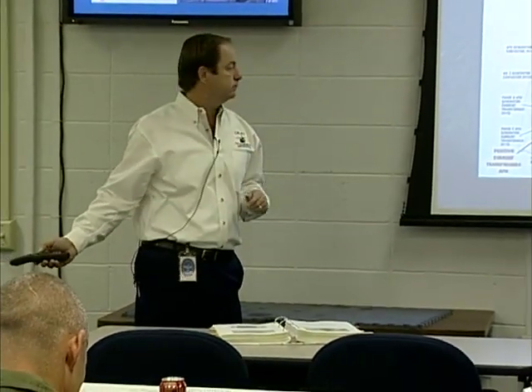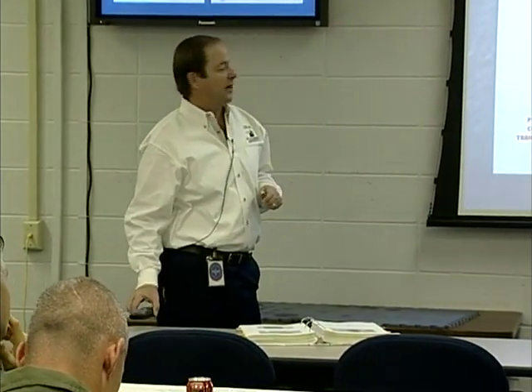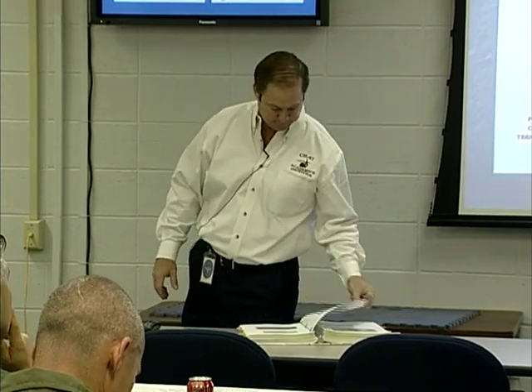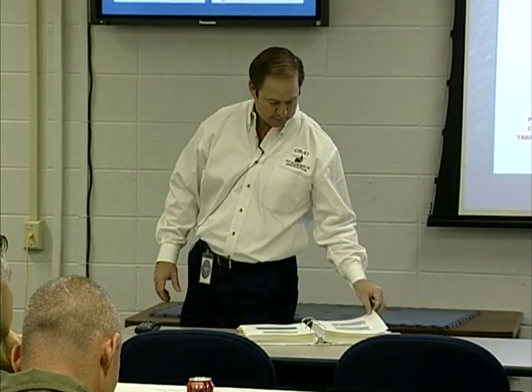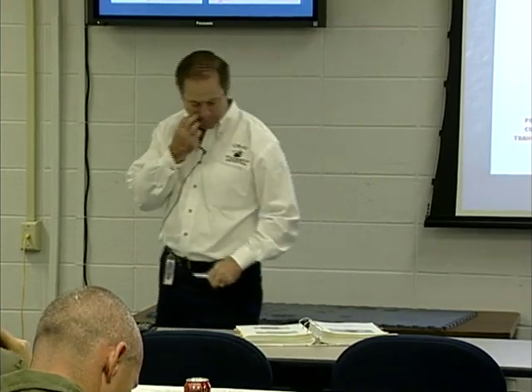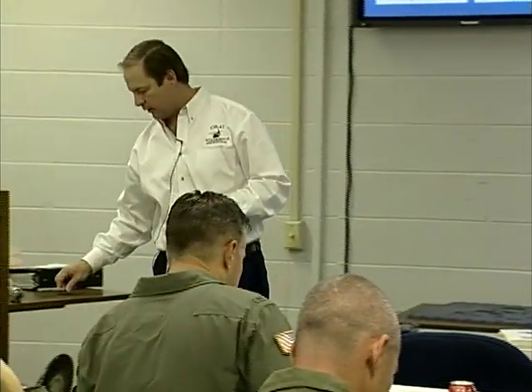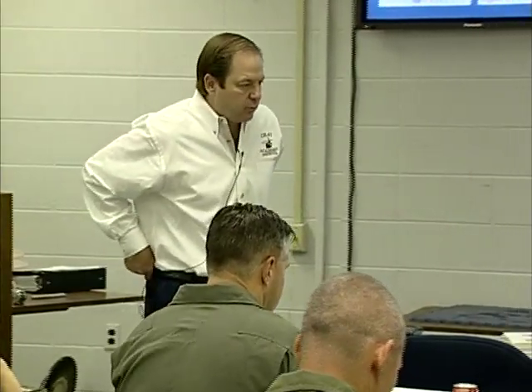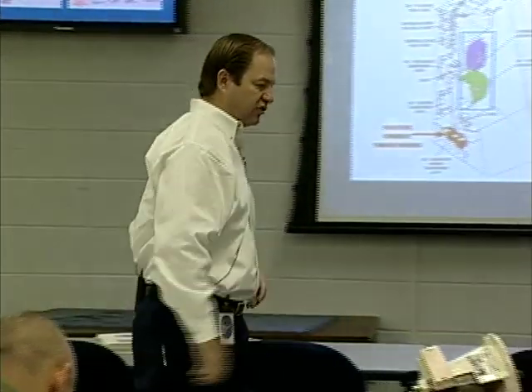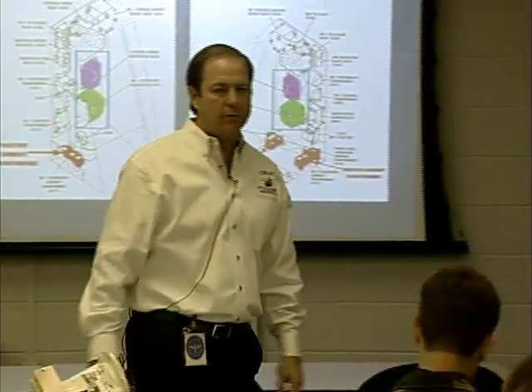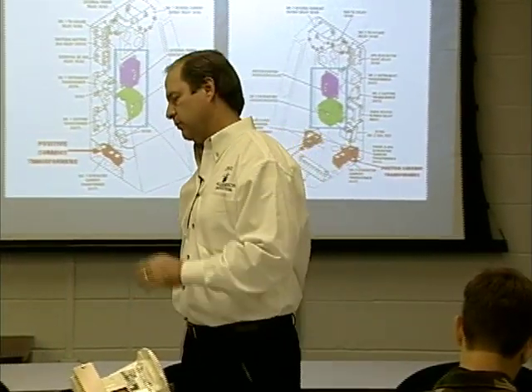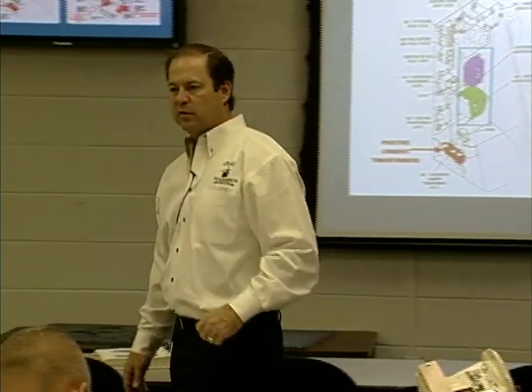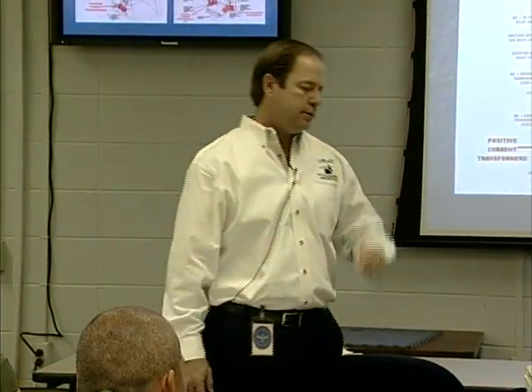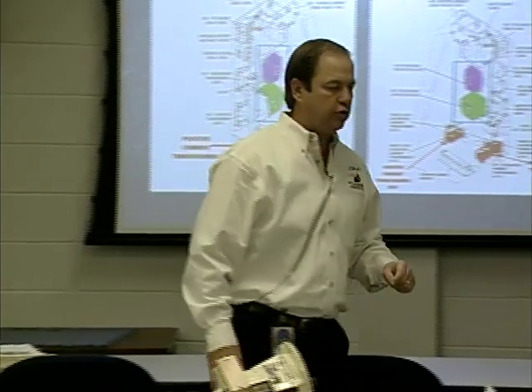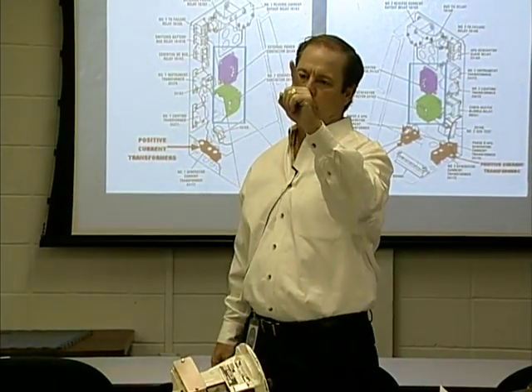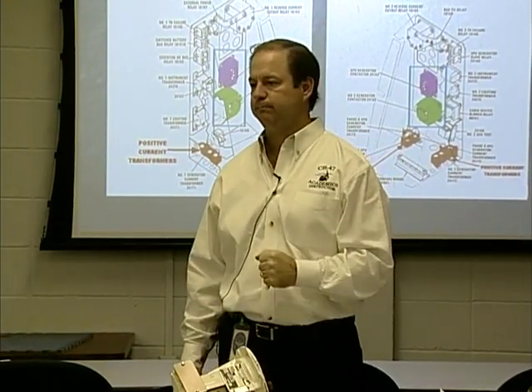Any questions about that? Now, the contactor relays. On the bottom of page 9, keeping in mind, when we talk about the contactor relays, it sounds complicated, but in reality it's going to provide for three things. What's it going to provide for? One, it's going to ensure that only one power source is connected to a bus at a time.